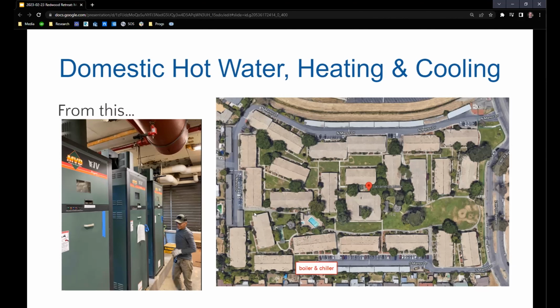They used to have an underground recirculation loop circulating around the entire property, which was immensely wasteful, and built in the 1960s, it was starting to fail regularly, with the owner having to dig up the property and patch the pipes. That was a strong motivating factor for the owner to get rid of it. The chiller was basically held together with bubble gum and duct tape, and the operator who ran it was retiring, and they were scared no one else could figure out how to run it.